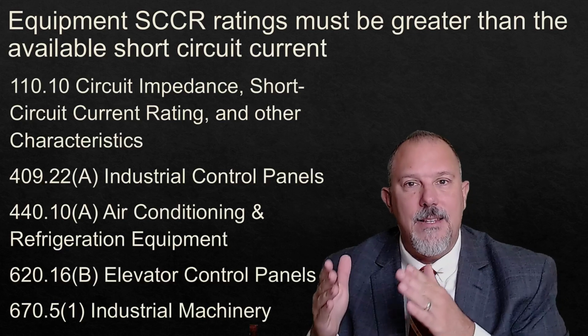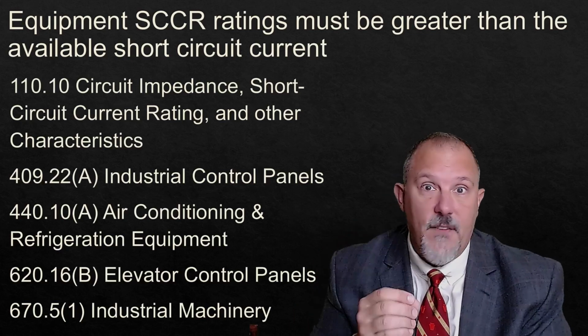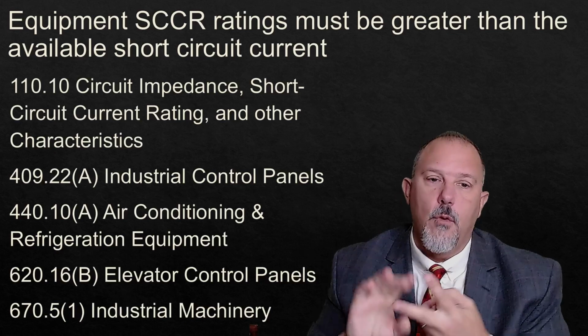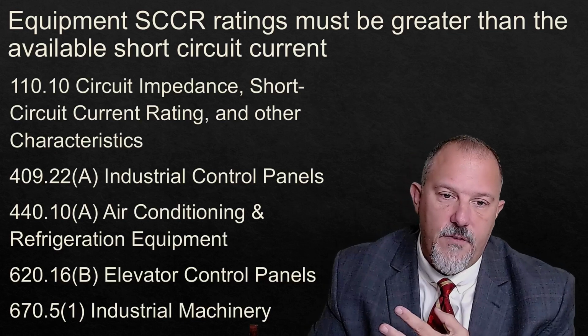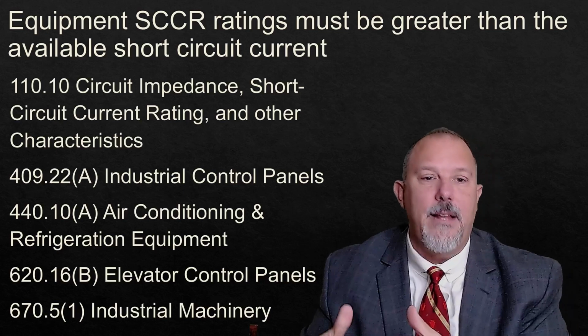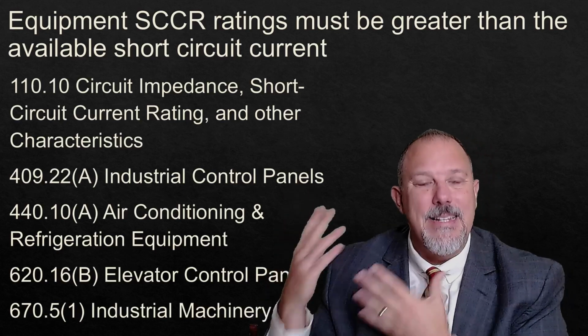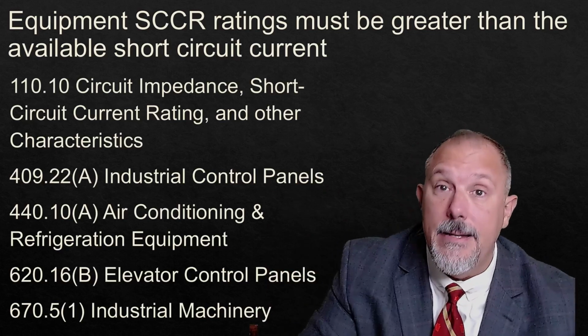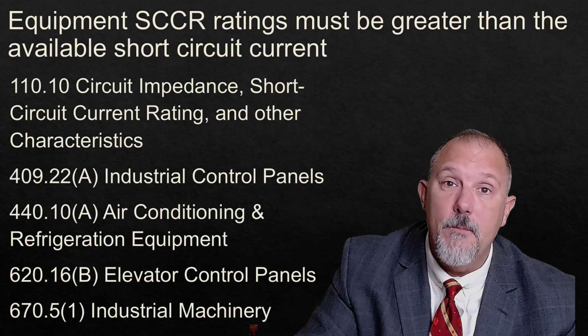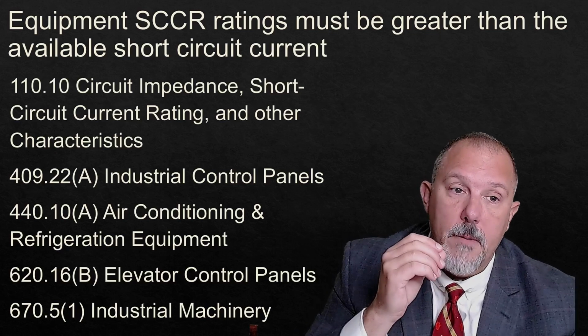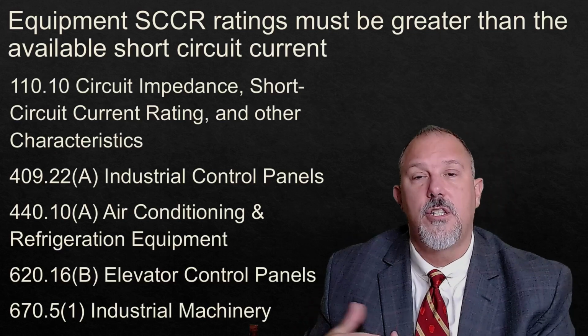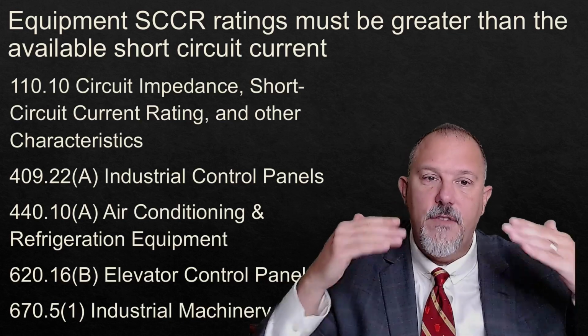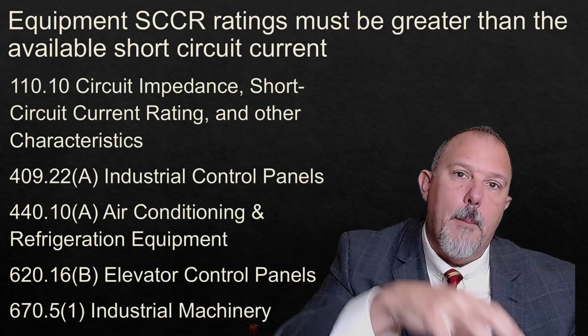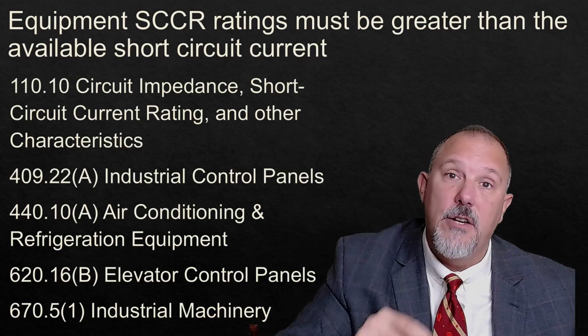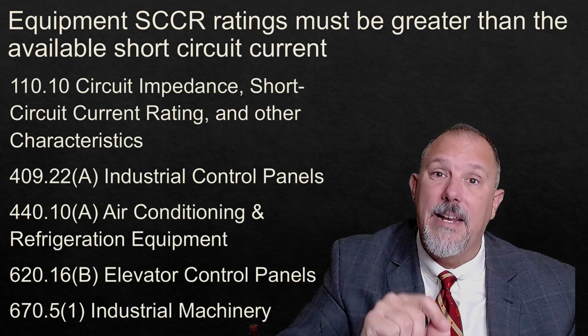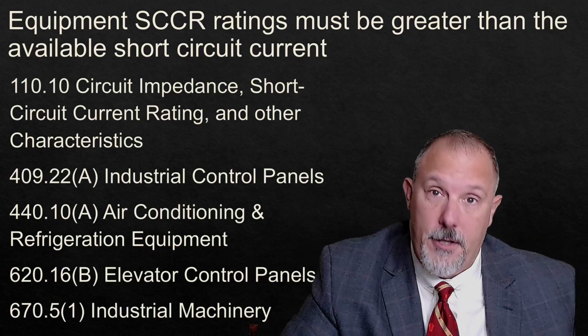They also added that specific language in 409 for industrial control panels, 440 for air conditioning, 620 for elevator control panels, and 670. Why would we add it in these other locations when it's already technically in 110.10? Because it's not getting done. People are missing it. They're not thinking about it. So we put that language in these other sections of the code to raise the awareness. You've got to make sure this equipment is applied correctly. Why? Because of those videos I showed you. When you exceed the short circuit current rating of equipment, it's ungood.